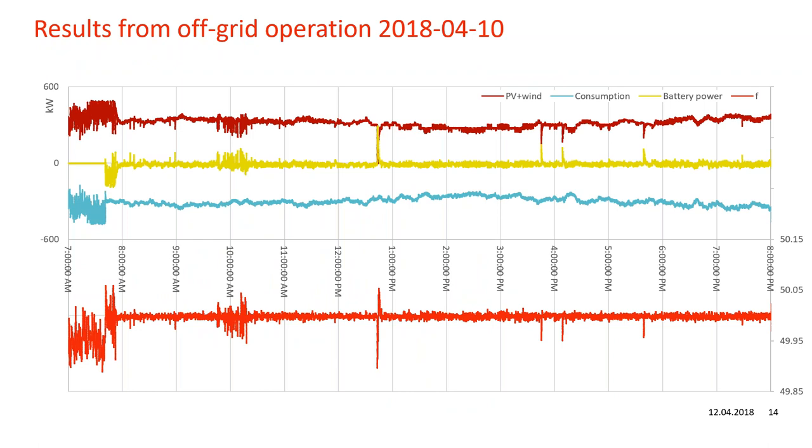These are results from more recent off-grid operations, from the 10th of April of this year. On the top graph you can see PV plus wind generation; the mid graph shows consumption; the yellow graph shows battery power; the red bottom graph is frequency. You can clearly see when we go off-grid and the frequency becomes more stable, as we have now optimized the control. In this specific case we ran the system off-grid for a full day to collect measurement points, and everything was very stable. You can clearly see how frequency is much stiffer when running off-grid compared to running as part of the interconnected Nordic system.